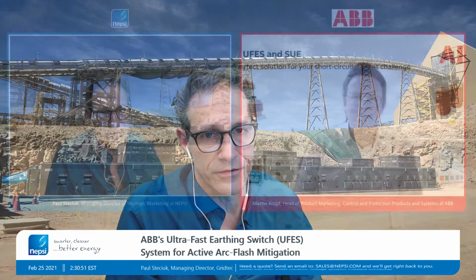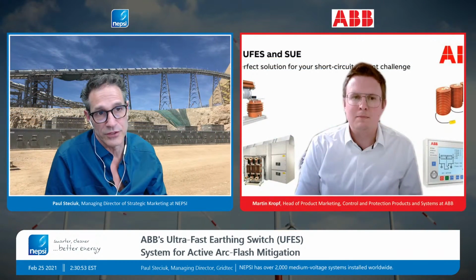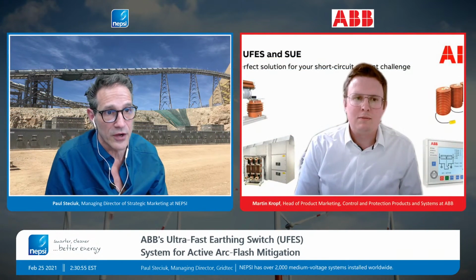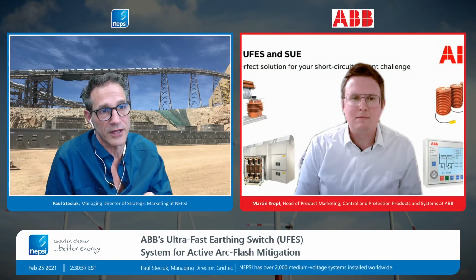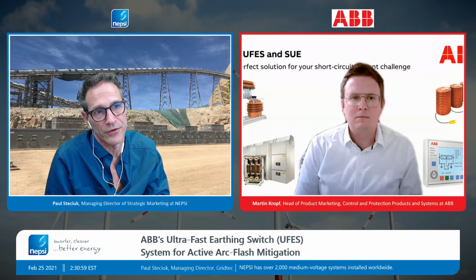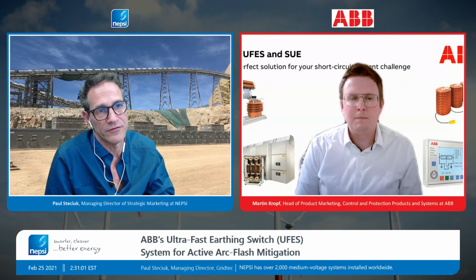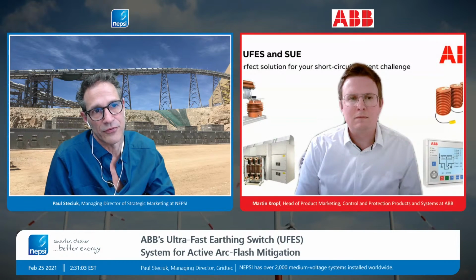That's an example of equipment that, if you were to have a fault, would fail the filter bank and potentially shut the mine down. Having the ultra-fast earthing switch in that project was desirable because they wanted to protect not only the people that operate the equipment, but also the equipment itself, because it's vital to the operation of the mine.